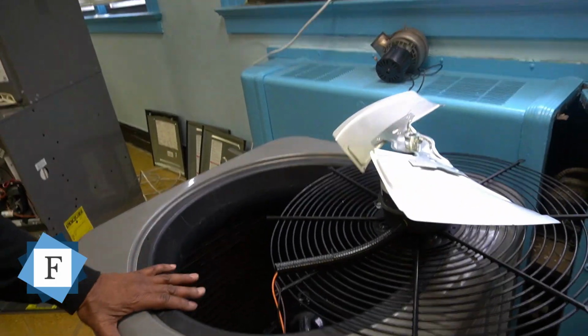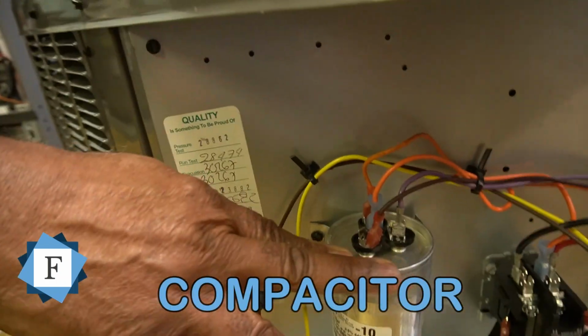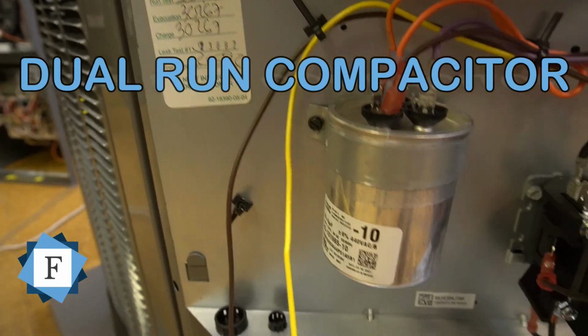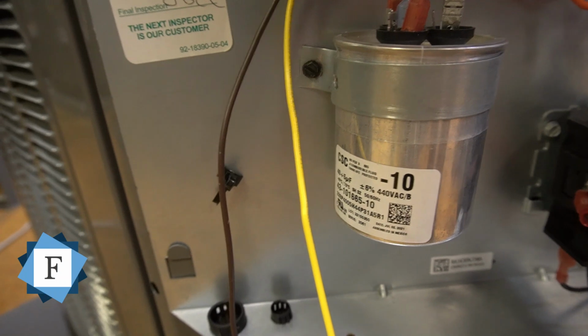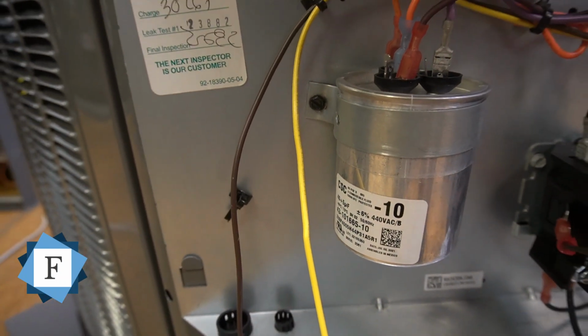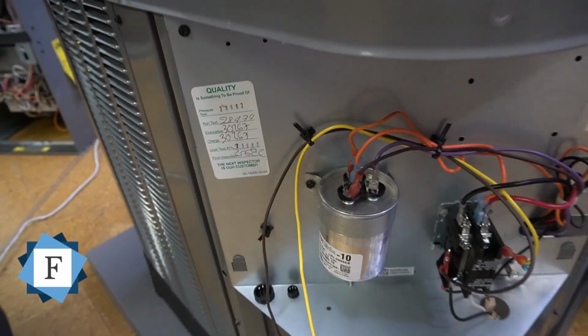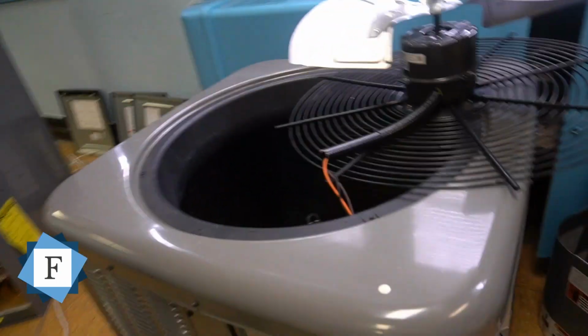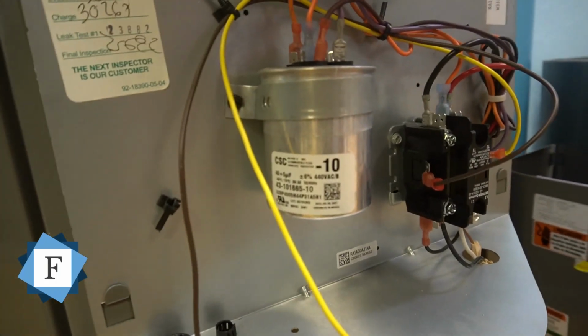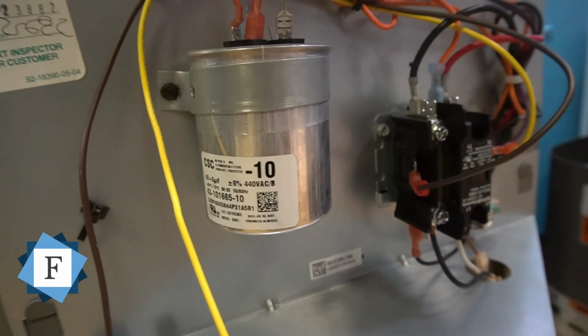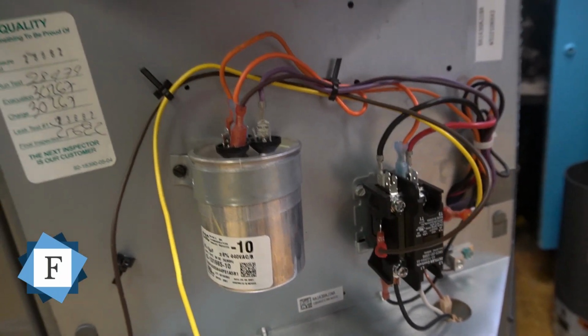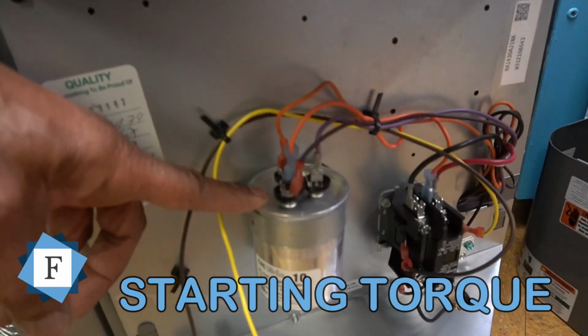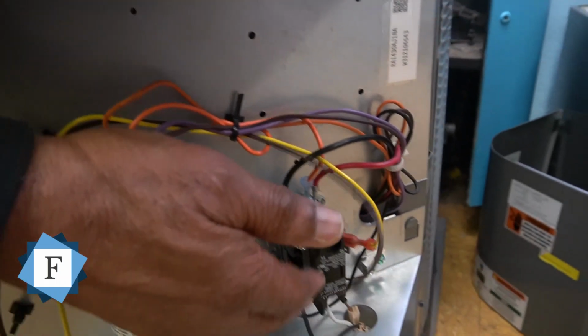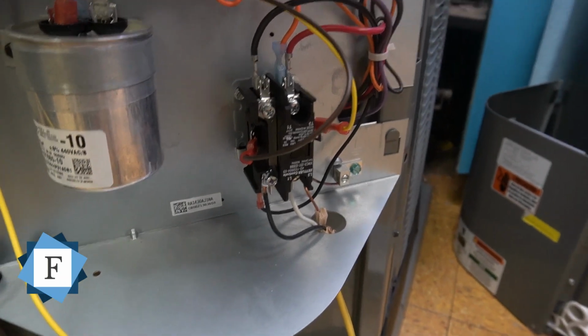We also have another device here called the capacitor. And this is called a dual run capacitor. They call it a dual run because it's doing two things, starting and running. Dual start run capacitor. And this is the device that gives the compressor and the fan the starting torque in order for it to start. And without that starting torque on a compressor, condenser, the unit will not start. So this is what starts it with that starting torque here. And this is the power, the 240 volts that powers everything here in the condensing unit.